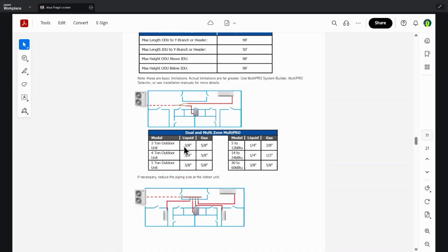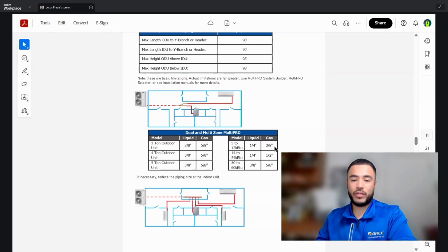So, moving on here, dual and multi-zone MultiPRO. As we stated earlier, these are the line set connections for the outdoor units. We know they're all 3/8, 5/8, so no confusion there. This changes from the 410A models, as 5 through 12K stay 1/4 inch to 3/8 line set connections for the indoor units, where before 3/8 would take us up to 9,000 BTUs, and it would change at 12,000 BTUs to 1/2 inch. So now 5 through 12 will be 1/4 to 3/8 gas and liquid, 14 through 24 will be 1/4 to 1/2 gas and liquid, and 30 to 60 is 3/8 to 5/8 gas and liquid.